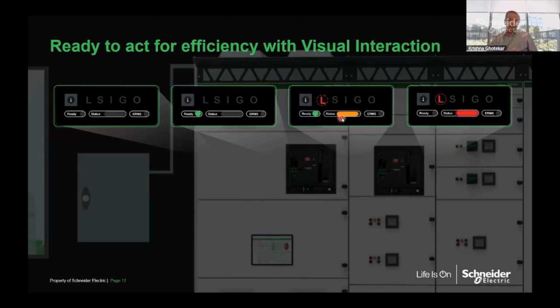In case the breaker has gone in overload more than 90%, so it's still not overload, but it's a pre-overload scenario. In that, the status will be amber and L will be indicated. That means it's from 90% to 100% of the loading. So you can take any preventive actions to avoid any tripping of the breaker. Then let's say the breaker still goes more than 100%, let's say 120% of the load for 30 minutes or 20 minutes as per the tripping curve of the breaker, and the breaker trips.